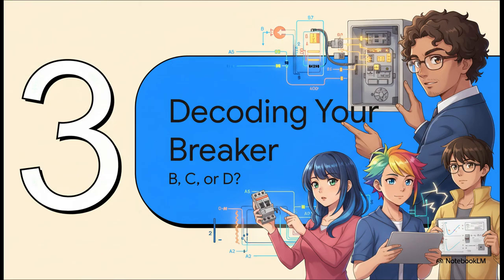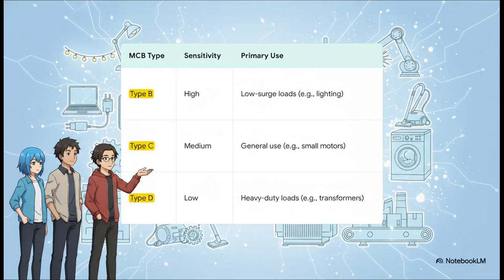See, not all circuit breakers are created equal. They're actually designed with different levels of sensitivity, specifically to handle different kinds of inrush current. The secret is decoded by that little letter printed right on the front of the switch. Now, in your house, you're really only going to run into three main types: B, C, and D. Type B is the most sensitive.